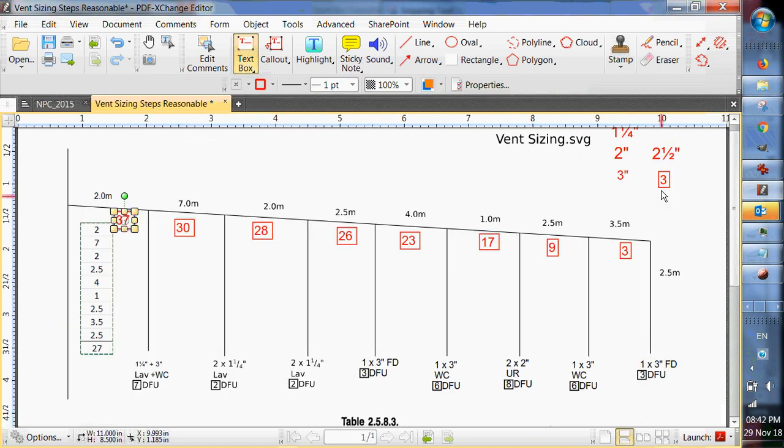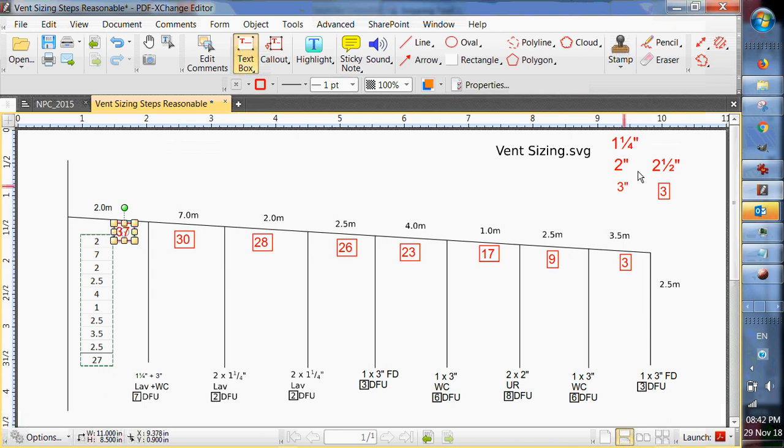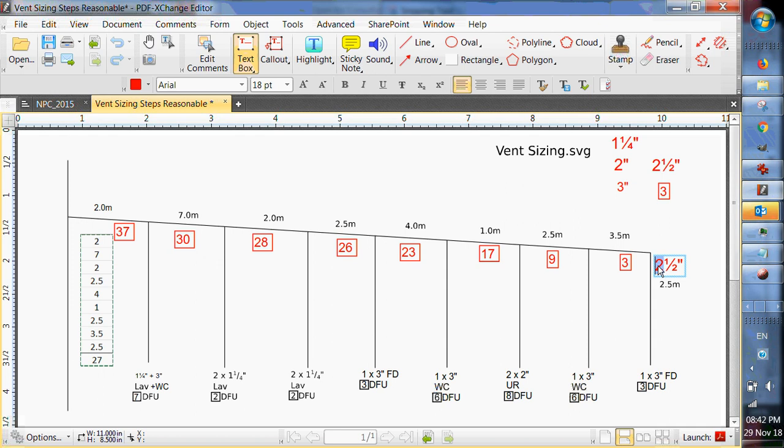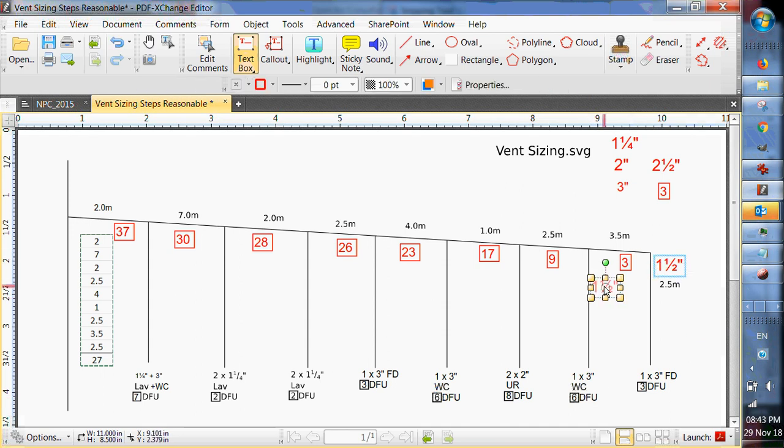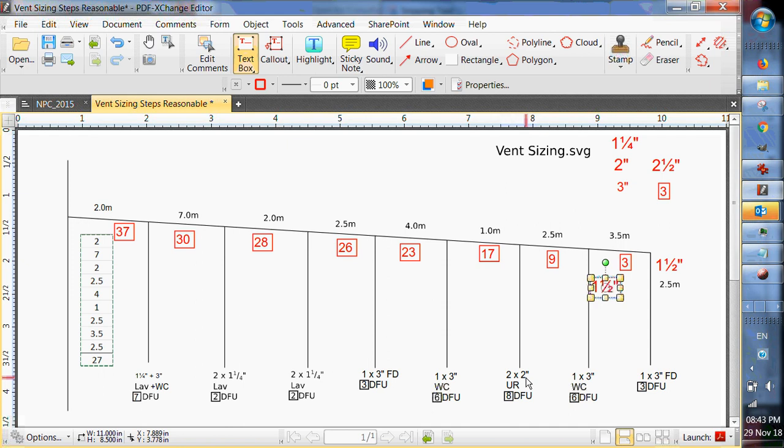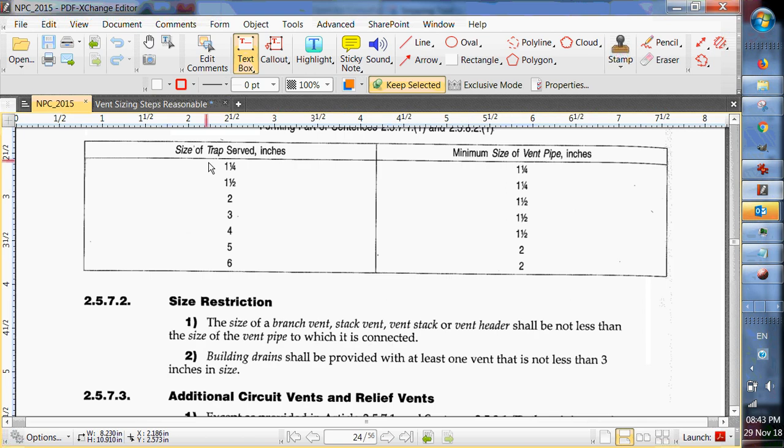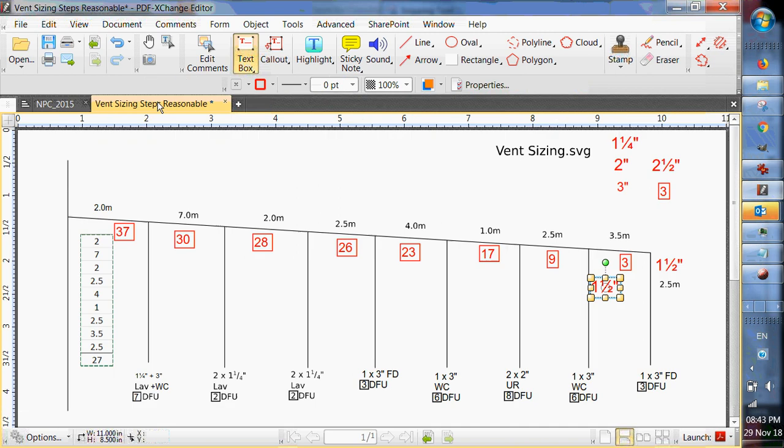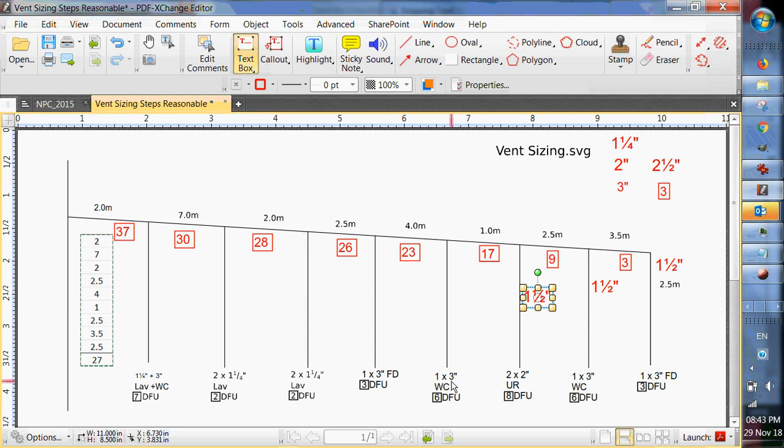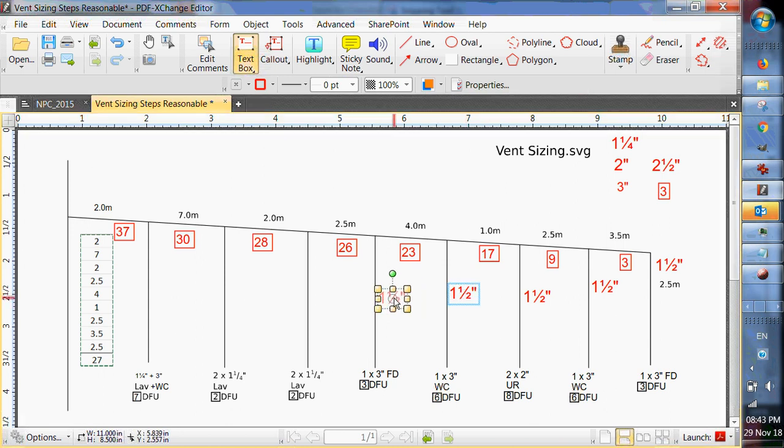Three inch floor drain takes an inch and a half pipe, so I'm going to put that here. Three inch again, so take another inch and a half. Two times two inch. So when I've got two fixtures I can get away with a single vent for both fixtures. So a two inch drain, what does that take? Two inch drain takes an inch and a half vent. Three inch. An inch and a half again. Three inch. An inch and a half.